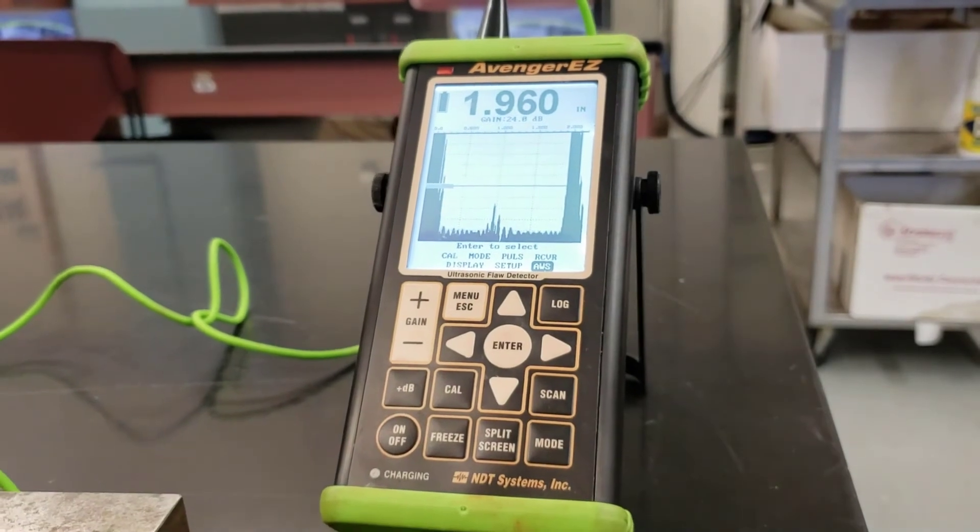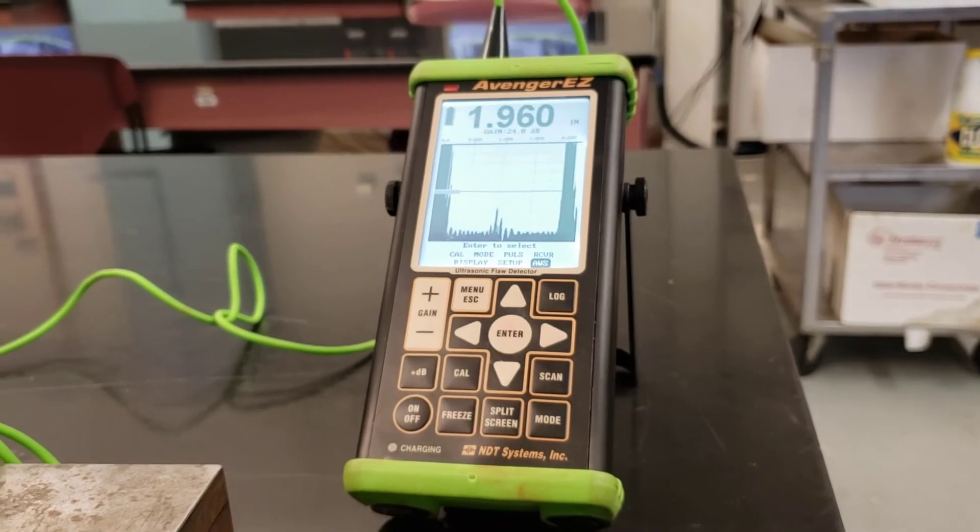So what you're doing is indicating that something between the thickness is interrupting the signal. That could be an impurity. That could be a hole. So we're using this for crack detection.